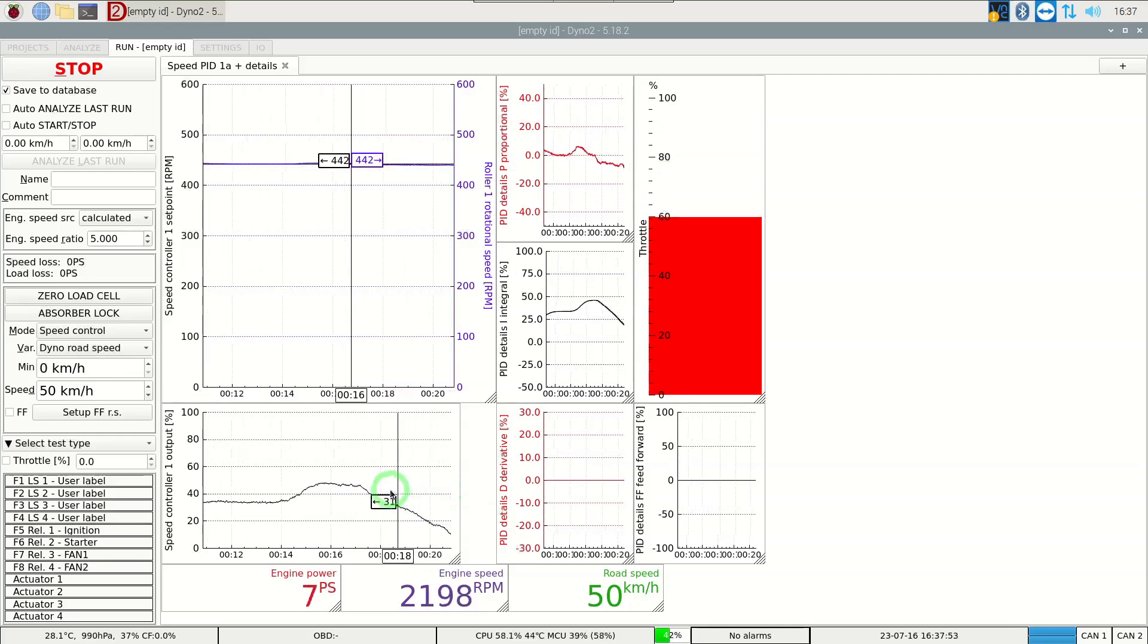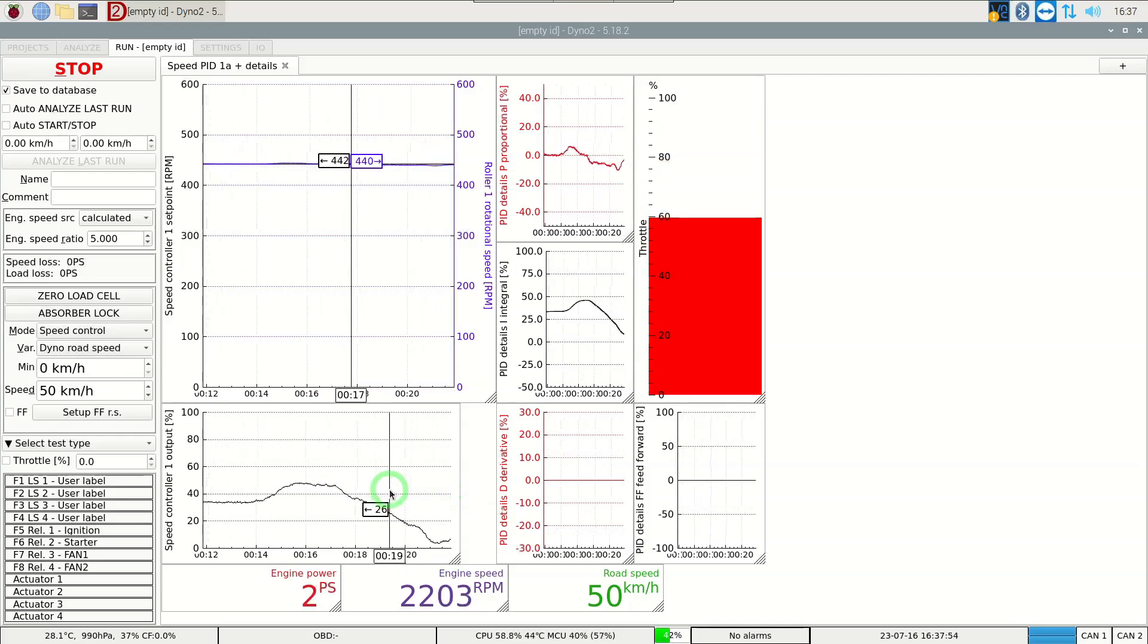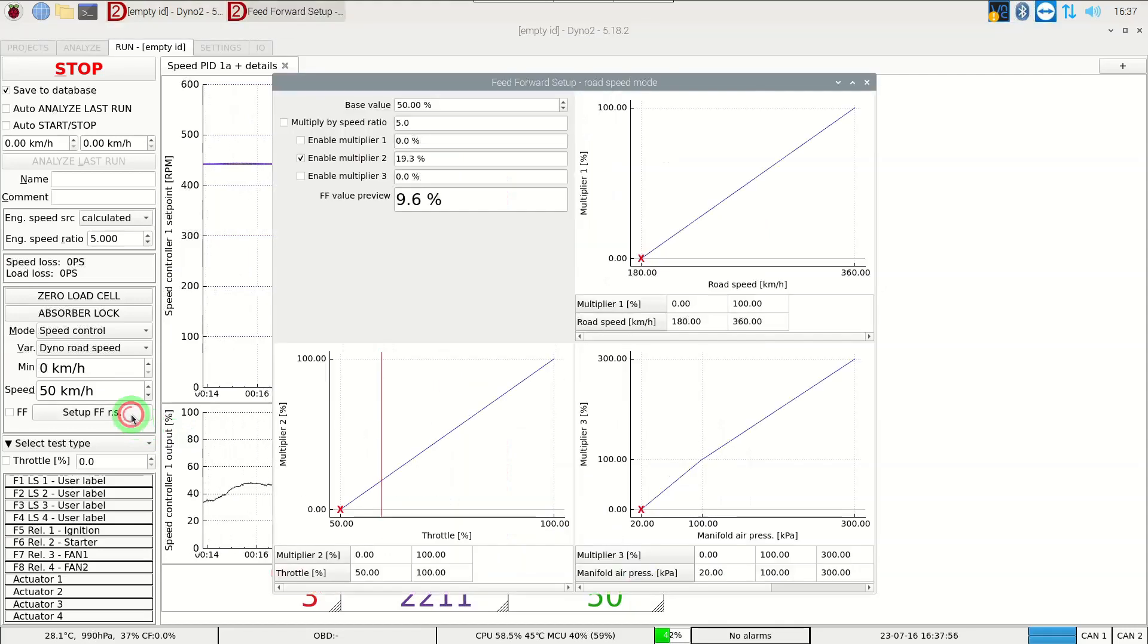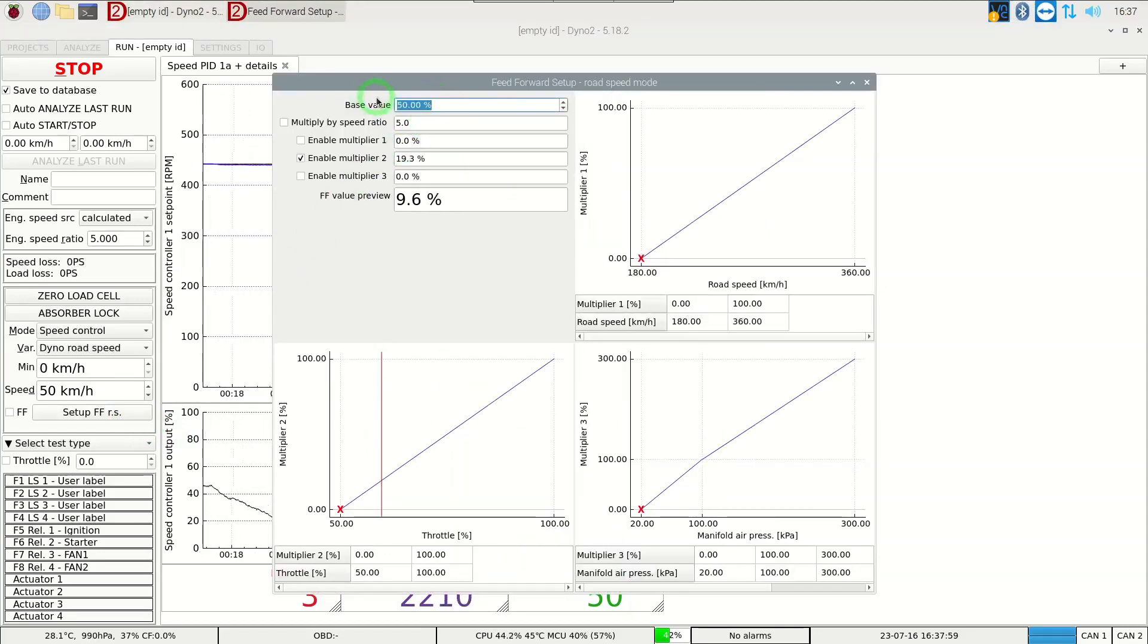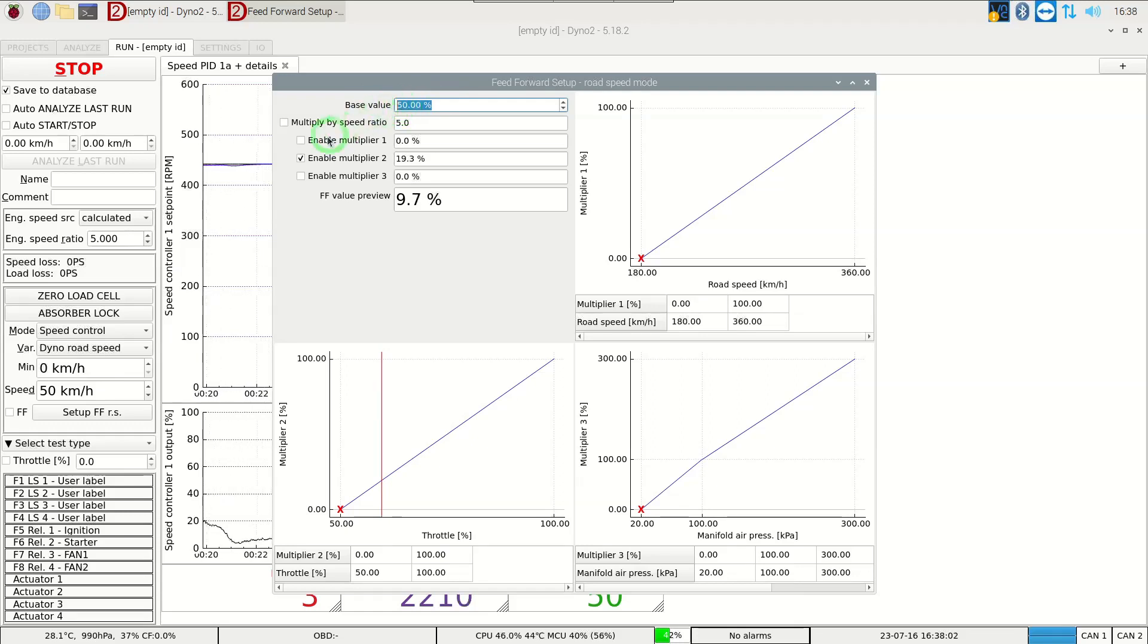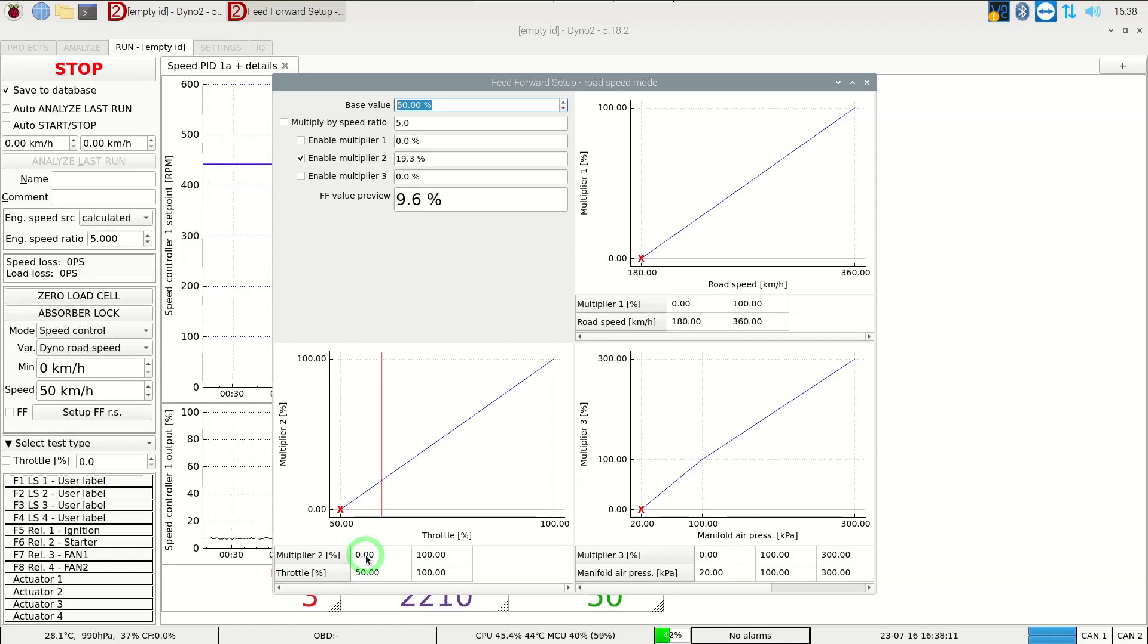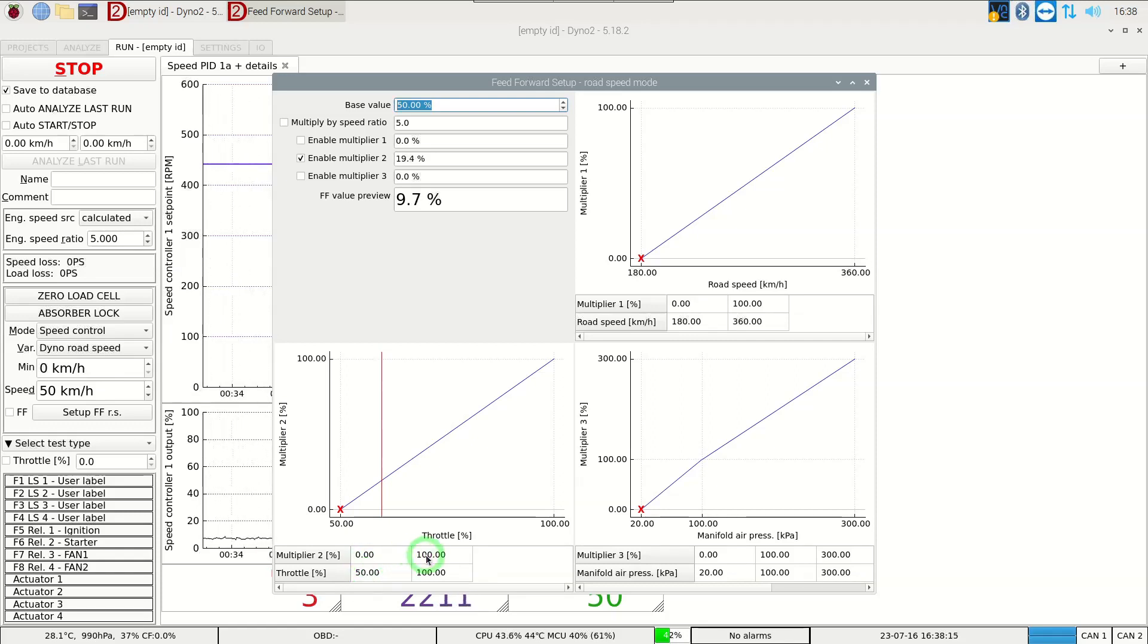We open the feedforward setup and set the base output value to 50%. Next we enable the multiplier 2 and set it to multiply the base value the way we noticed. 0% of base value at 50% of throttle and full base value at full throttle.